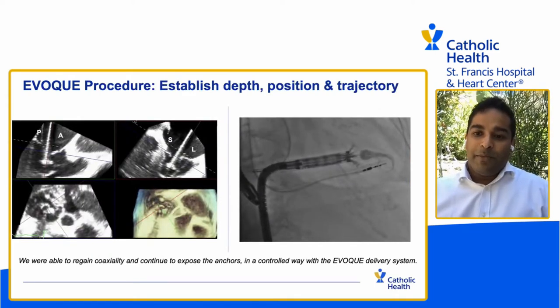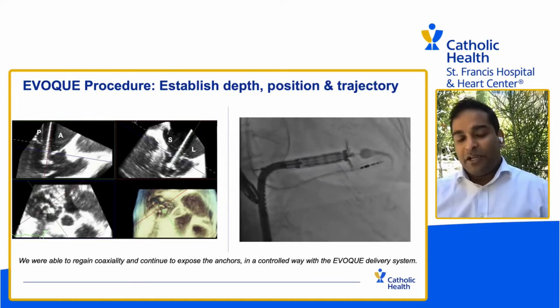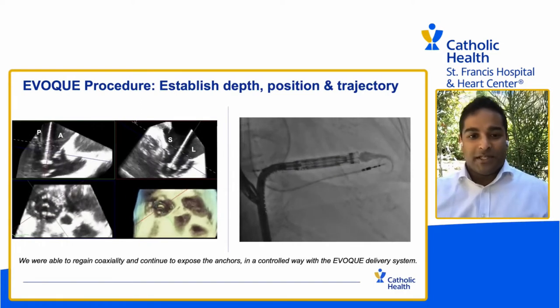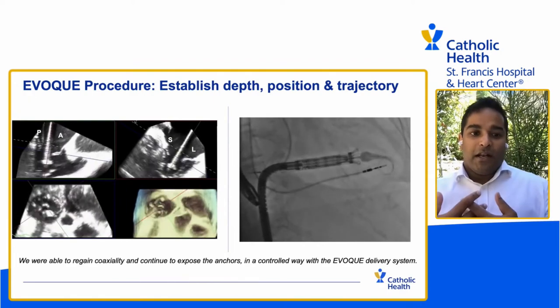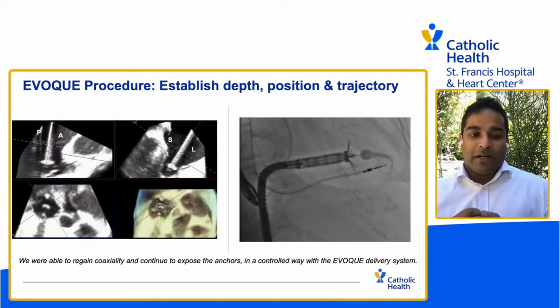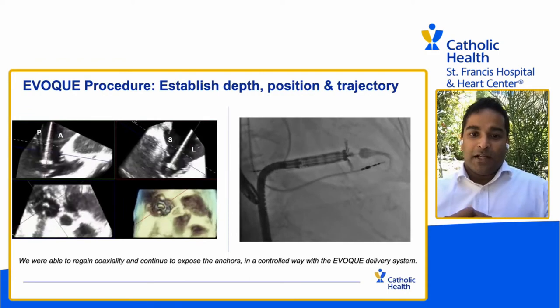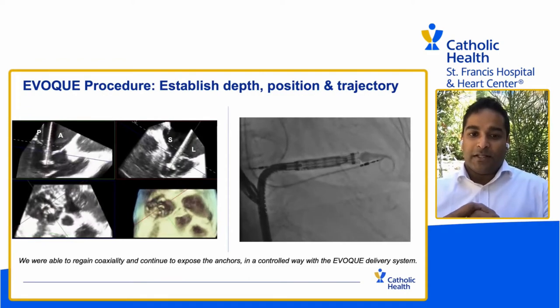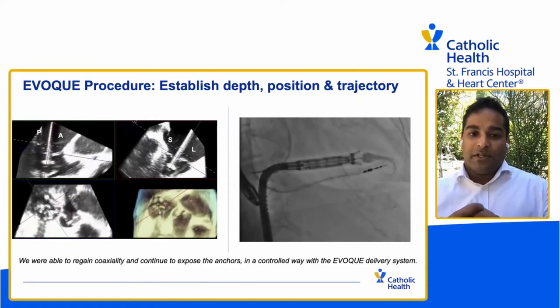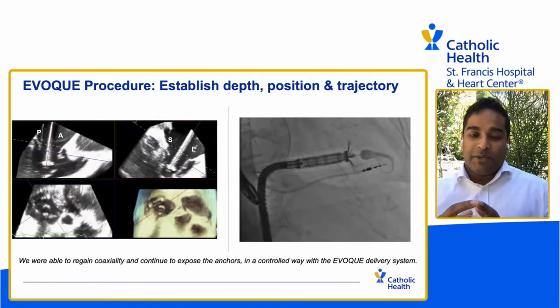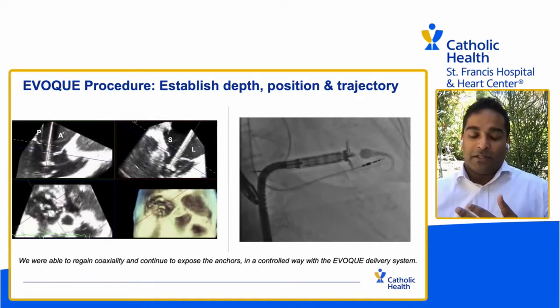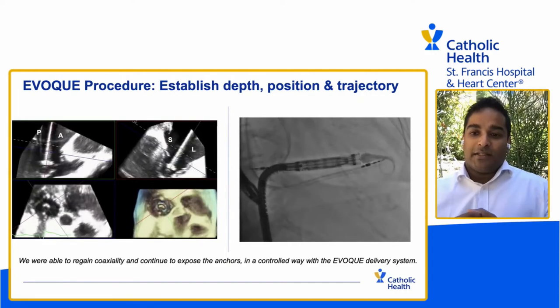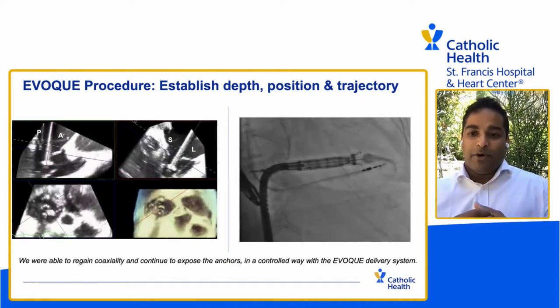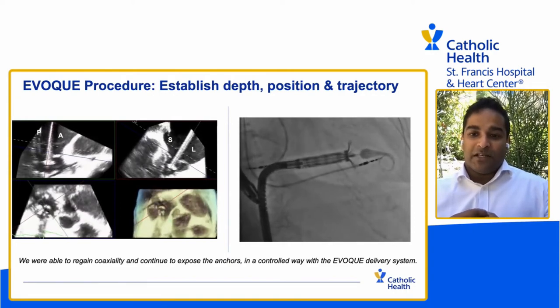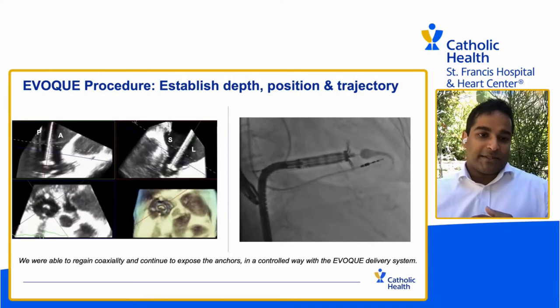Once we're happy that the capsule gap is in the right place, we take a brief procedural timeout, because at that point in time, if we can't align the valve properly with regards to trajectories, or can't get adequate depth with regards to the capsule gap, we can remove the device from the patient without any consequence. As soon as the anchors start being deployed, it becomes a little bit more difficult to remove the valve because we can't recapture this device.